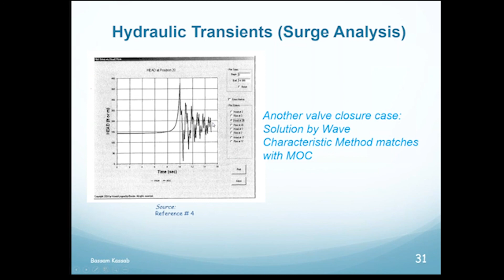And how do you deal with transients in a pipe? As I said, the thickness and the grade of the pipe has to be suitable for the transient. You can minimize the effect of the transient by having a surge tank or an air surge tank like this, air chamber, same idea, but with the air chamber it's closed on the top and the air gets compressed here. But with the surge tank, the water level can go up and down. So you install that in your system, so when you have a transient, the surge tank or the air chamber can take most of the shock.